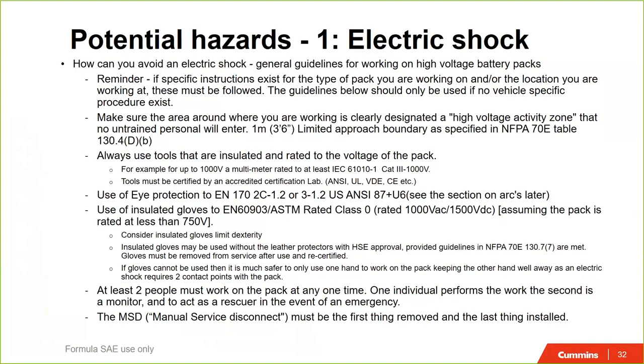Eye protection, insulated gloves - assuming the pack is less than 750 volts, class 0 gloves will keep you safe. Bear in mind that gloves need to be tested every time you put them on. They should be inflated and checked for leaks. If a glove leaks air out, it is not going to protect you.